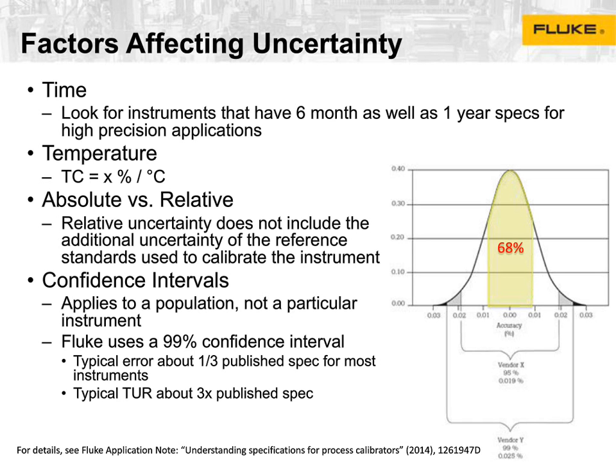And at that point, you need to get the unit warm again because you're going to start having errors in your response. So the compensation is really designed to handle the less extremes, down to 0, negative 10, or up to 50. And will basically just help you get the most accurate measure you can, or at least tell you how much error you're adding. And you can't always control that. And that might be a decision where you say, hey, this is so high accuracy, I have to have it more accurate. So maybe that's when you take the unit out of commission, remove it from the system, take it back to the shop, and do it at the bench. Does that answer your question?